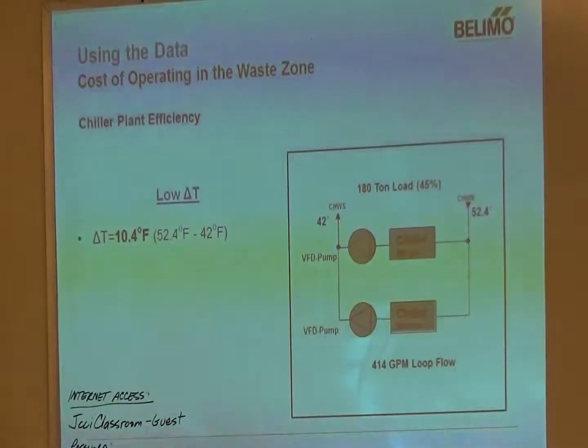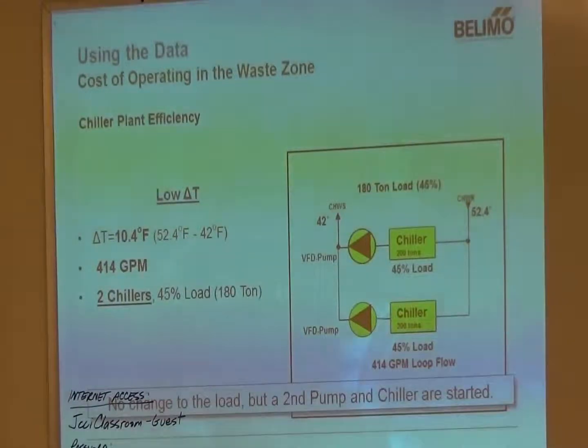Now what's going to happen if we start seeing some low delta T, we drop down to 10.4 degrees because our flow has increased to 414 GPM. Notice though that the load has remained the same. However, we're requiring more flow to meet that same load. Well, as you can see, what's going to happen is because each chiller can handle 200 tons, we actually have to bring on a second chiller, not because our load's changed, but because the amount of water we're flowing through has gone up to 414 GPM, and each chiller can only handle 400 GPM. Or, I'm sorry, 200 GPM.